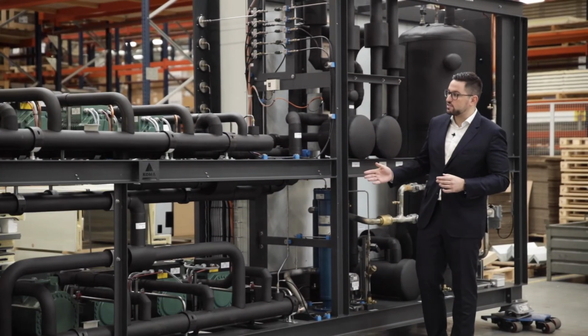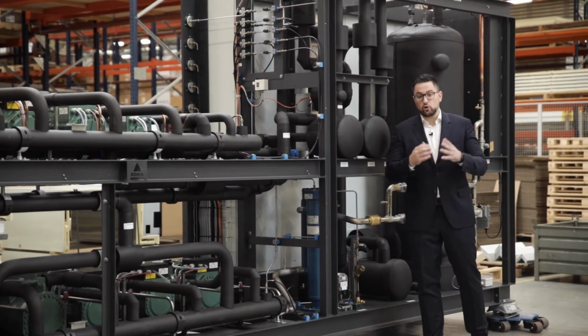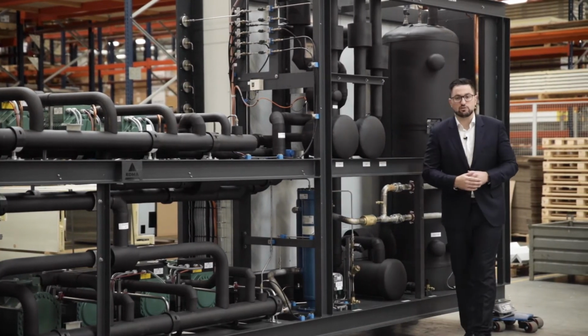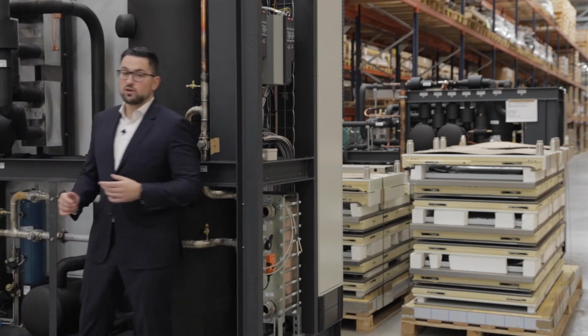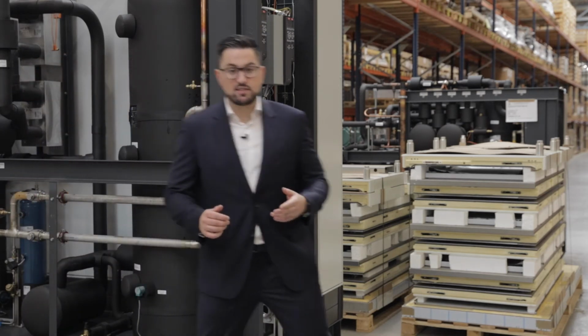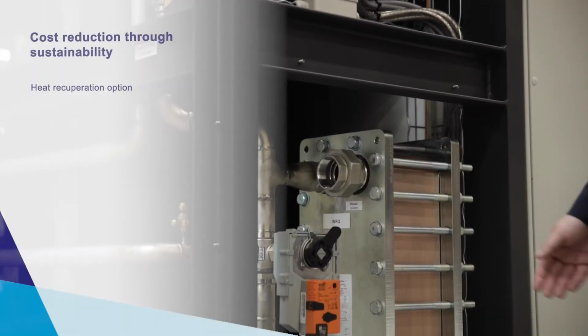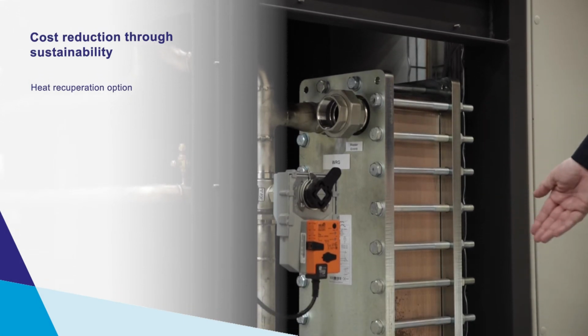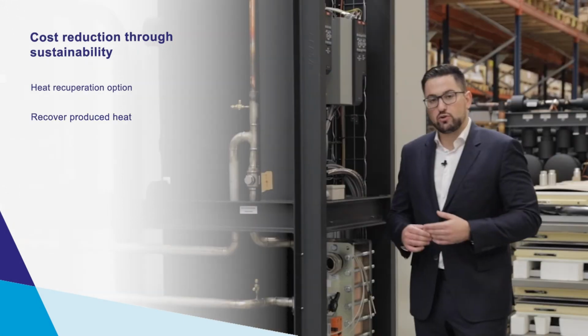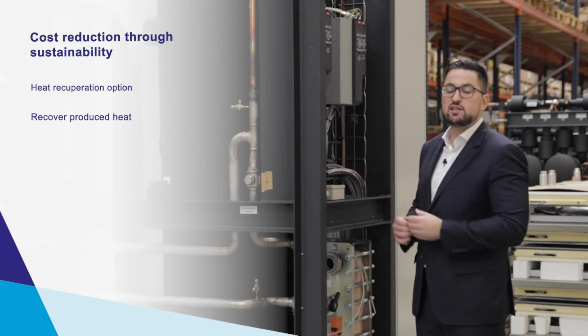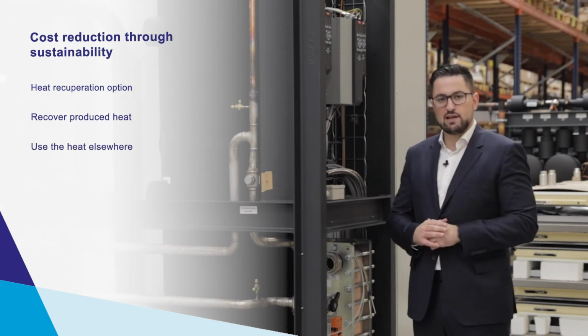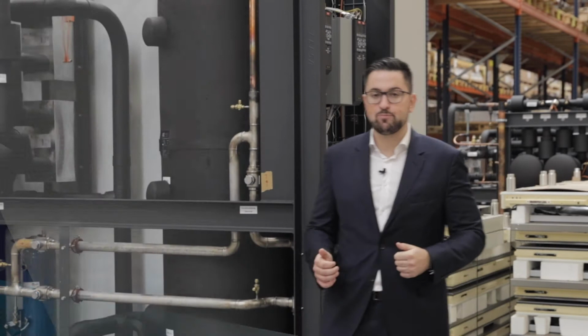The compressors that you see here are completely dependent on your cooling outputs needed and the equipment that you're using. Furthermore, your CO2 Booster system is able to come with a heat recuperation option that you can see here. With this heat recuperation option, you can recover the produced heat from the machines and use it elsewhere in your production plant, like your floor heating.